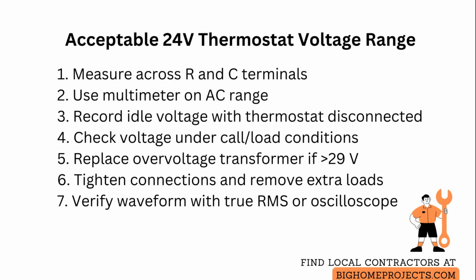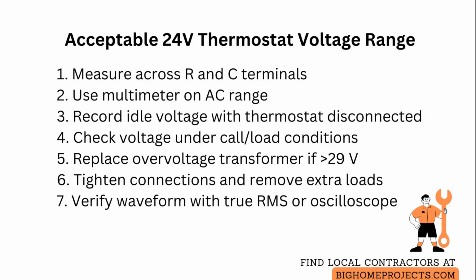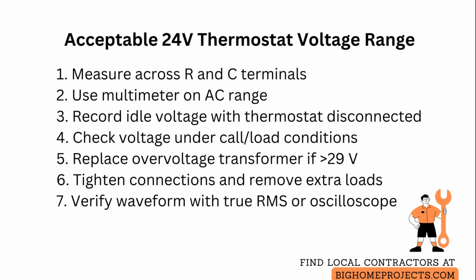Under call conditions, when heating or cooling is engaged, the voltage will sag slightly. A healthy transformer typically holds within the acceptable range and drops no more than a few volts under load.